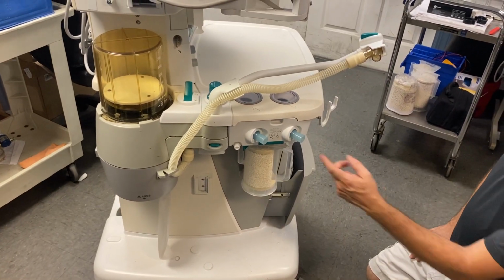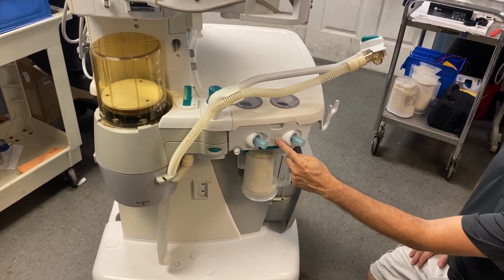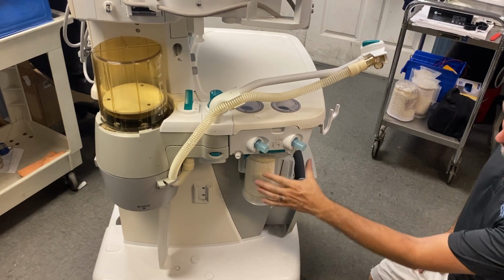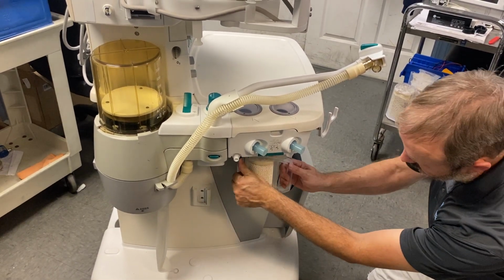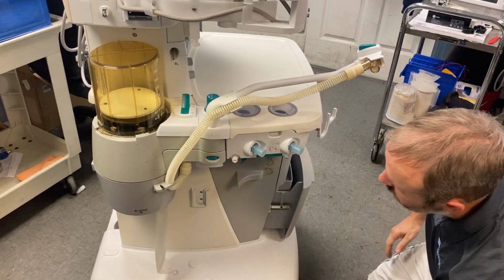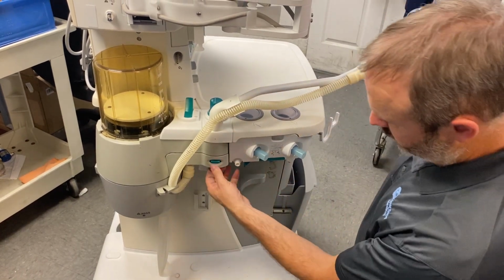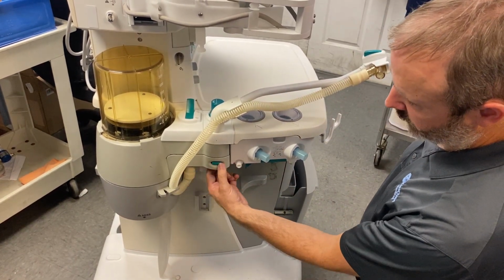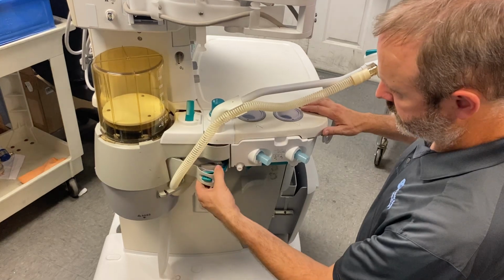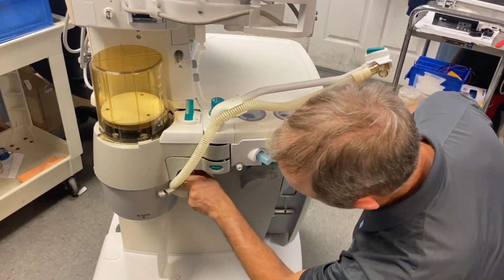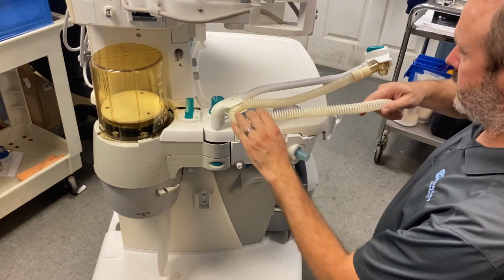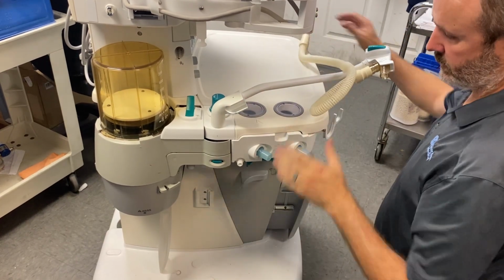So in order to change the breathing circuit module behind the flow sensors, if you've got a canister on there, you just need to remove your canister. You're going to press the green button on the breathing system. Oh, before you do that, disconnect your hose here and set it off to the side.